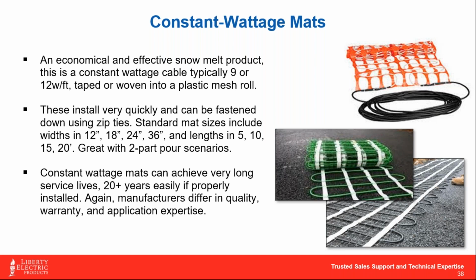Typically, for this application, with prefabricated kits, these cables are 9 to 12 watts a foot, tightened up in terms of their serpentine closeness. If we're using something like a mineral insulated cable that we bend the radius ourselves into the sidewalk, those are spaced about every 6 inches apart, and the cable itself is spec'd around 25 watts a foot. So when we turn it on a 6-inch radius bend, we're effectively getting 50 watts per square foot.